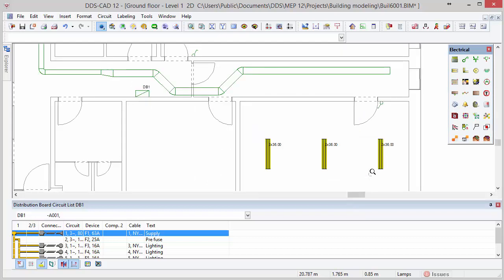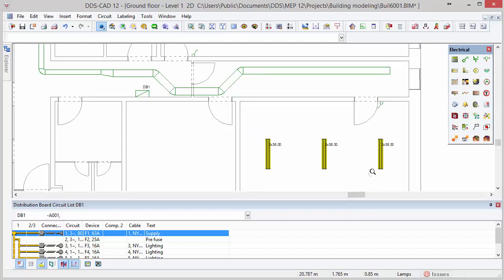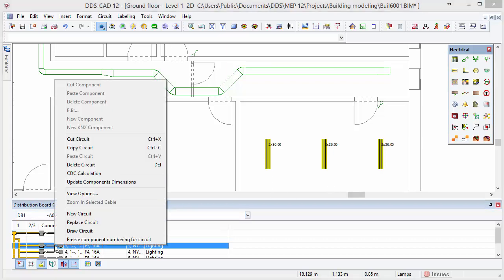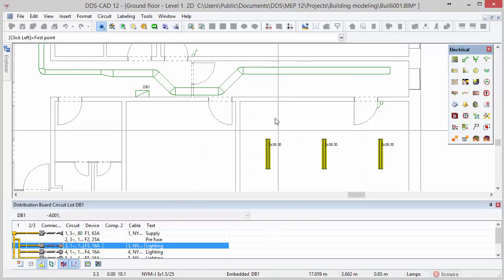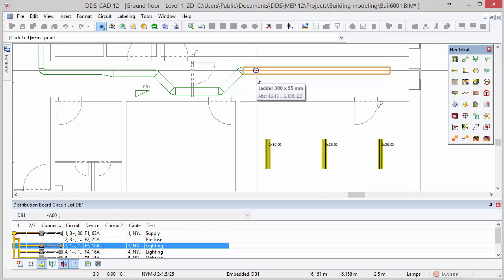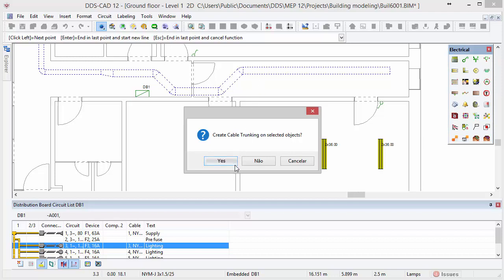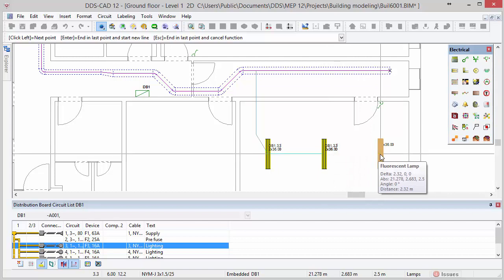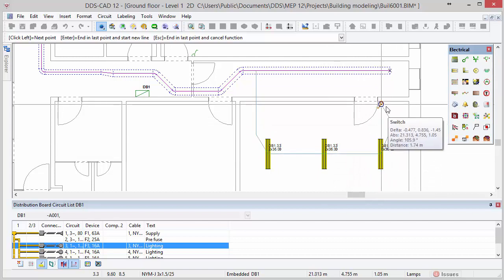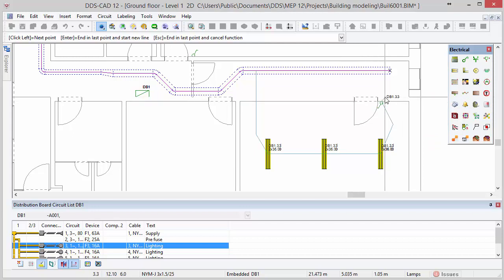Next zoom in to the bottom right room. To start drawing the circuit, select circuit number 3, right mouse click to open the context menu and select the option draw circuit. In this dialog we can configure the cable and check the conduit checkbox. Click OK to start drawing the cable. In this case we start the cable from a point leaving the cable tray. Make sure that the function SmartSnap is activated. DDS-CAD asks you if you want to create a cable trunk on the cable tray — click Yes. Now draw the cable and connect it to the lamps and switch with a left mouse click. When finished press Esc.